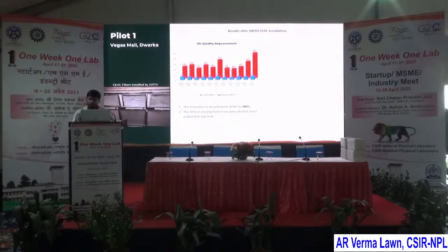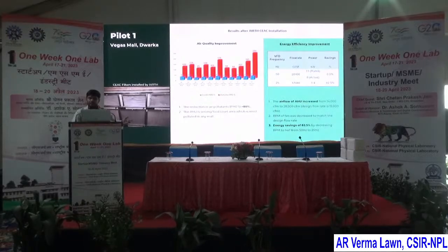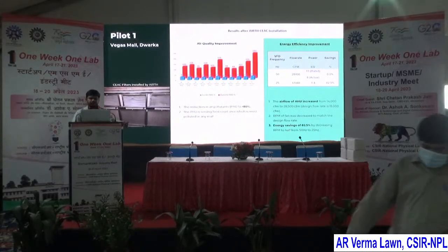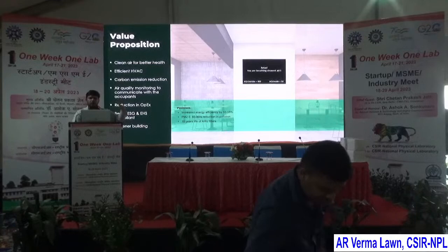So even when we are serving the food court area for a big building, which is like the most polluted area in any mall, we were able to get really good air quality, more than 80% always. Then second was the energy efficiency that we were able to achieve. Around 82% of energy we were able to save here on the AHU blower. How we were able to do that is because after installation of our system, the airflow increased from 14,000 CFM to 28,500 CFM. Now to match it again to around 15,000, we decreased the frequency or lowered the RPM, and that helped in decreasing the power. So efficiency as well.